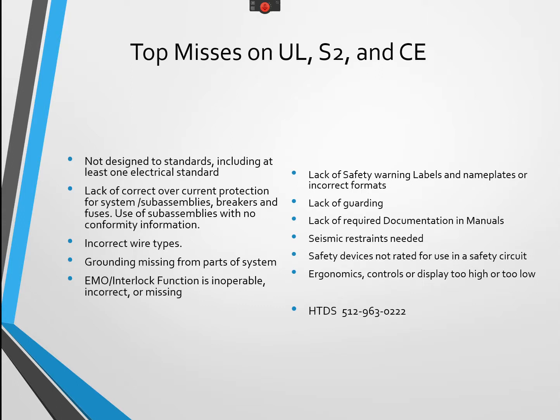What's more difficult is interlocks that are not there or are incorrect, or they're on the drawings but not on the machine, so they're missing. All those interlocks, which are safety interlocks, need to be implemented using safety-rated devices so that they're correct, and they need to be implemented using the correct safety relay. Then the wiring between them needs to be correct as well. That's typically going to be low voltage wiring, so you don't want to run it with any of your power wiring. If you have questions, ask me on that.